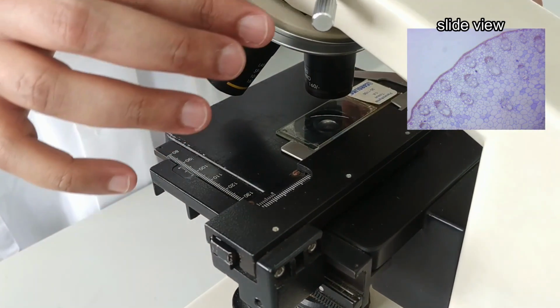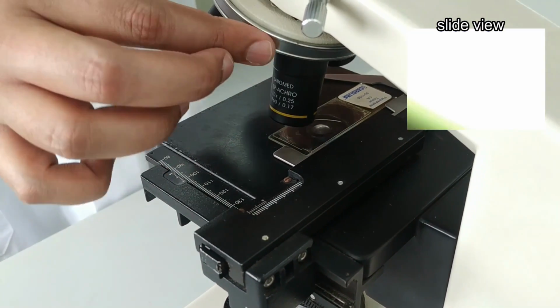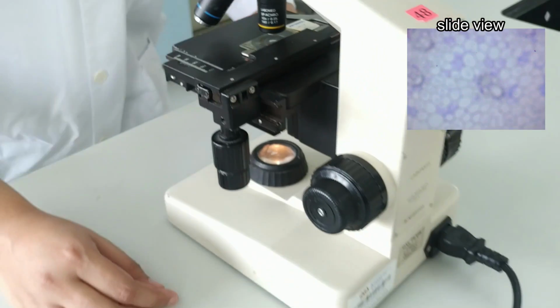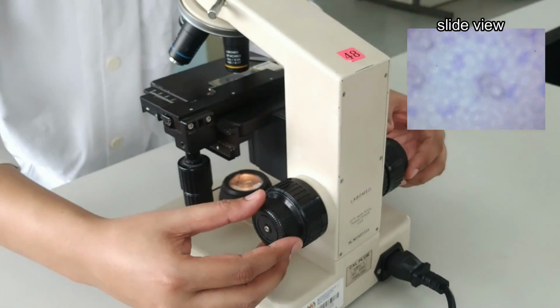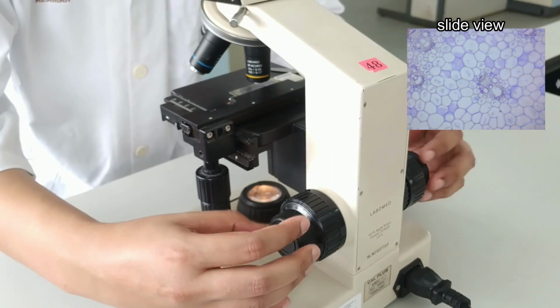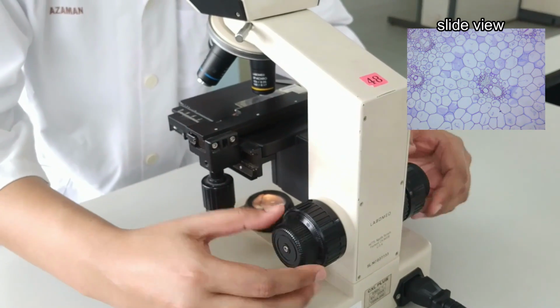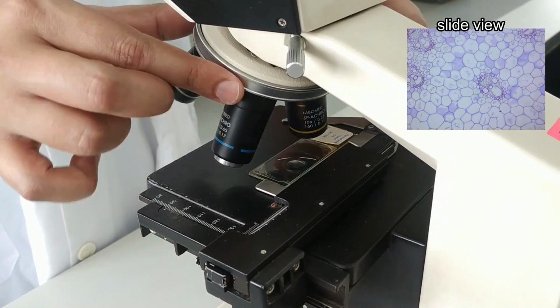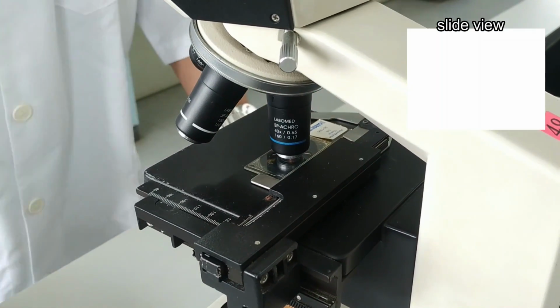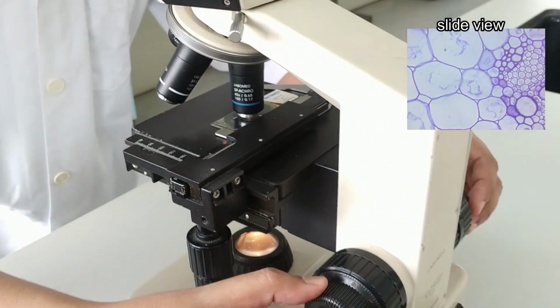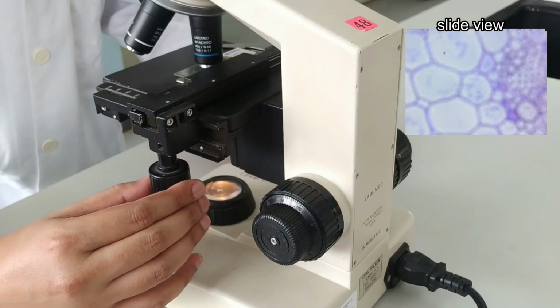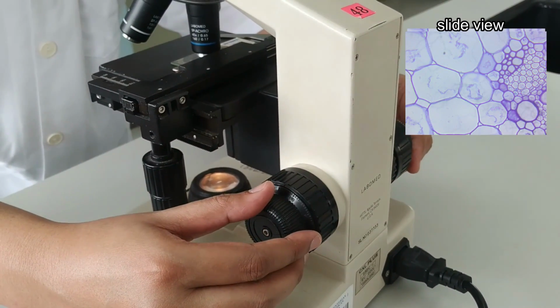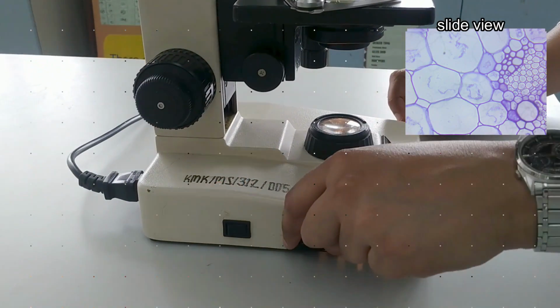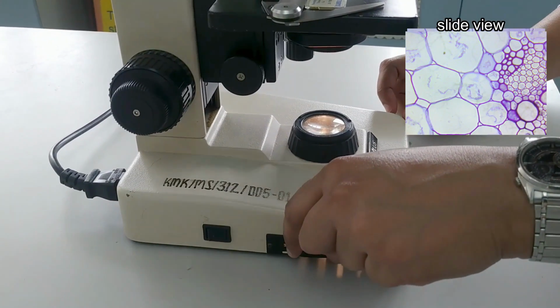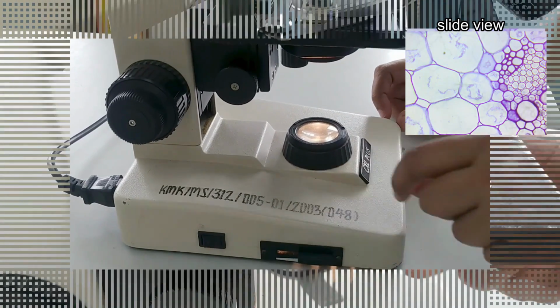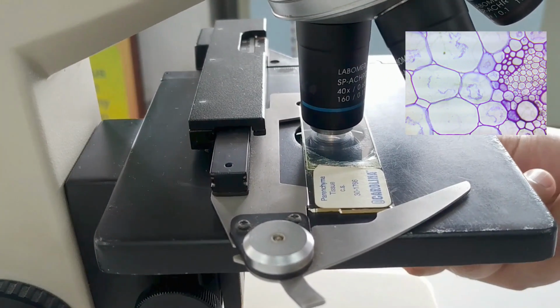After the specimen has been focused, rotate the nose piece to change to the low power objective lens. Refocus the specimen using the fine focus adjustment knob. After the specimen has been focused, rotate the nose piece to the high power objective lens. Refocus the specimen using the fine focus adjustment knob. Adjust the amount of light that enters the slide using the light control knob and the diaphragm knob.